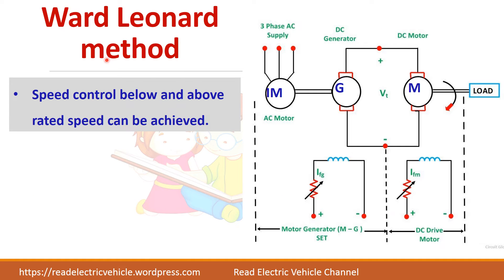The Ward-Leonard method looks a bit complicated but is very easy. It was used in earlier days, before the invention of power electronic devices. This motor here is the motor whose speed we want to control. The two techniques are: armature voltage control for below base speed, and field control for above base speed. By varying the field, you can control the speed of this motor above rated speed. For below rated speed, instead of putting a resistor to control the voltage applied to the motor, we have a generator which will supply the required voltage to this motor.